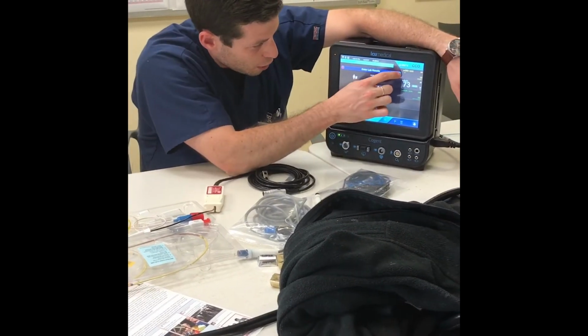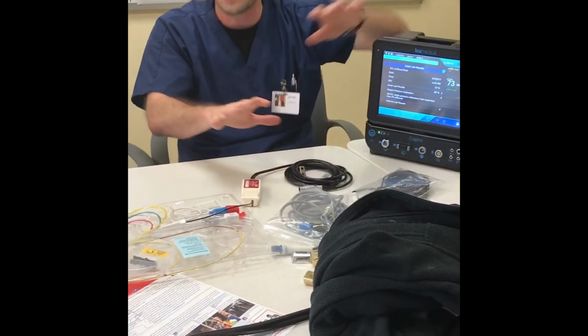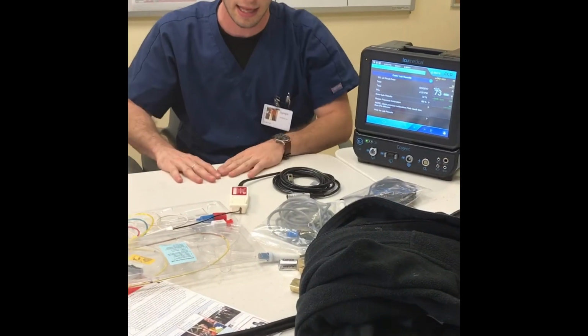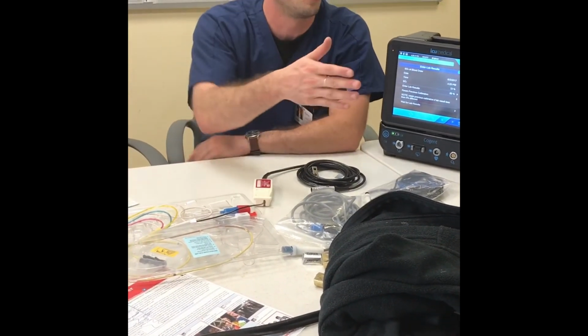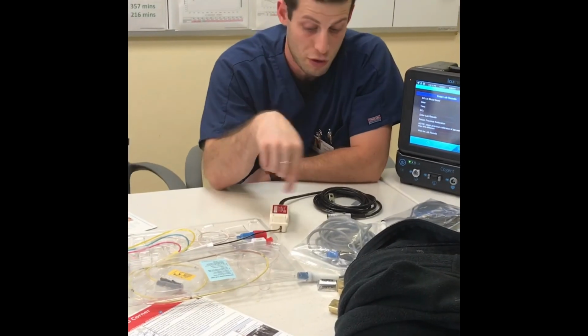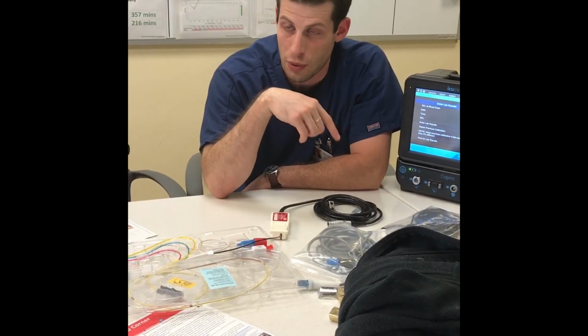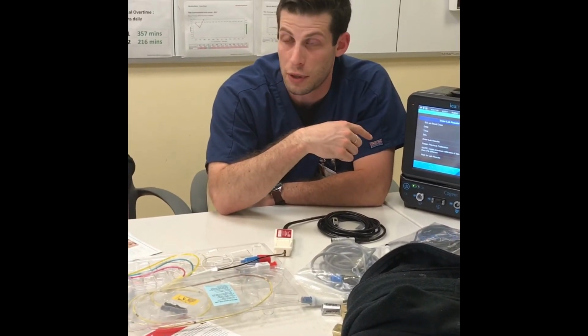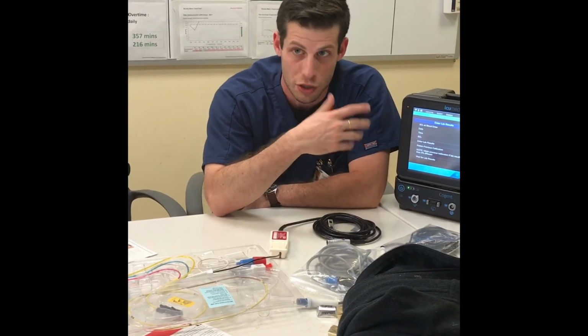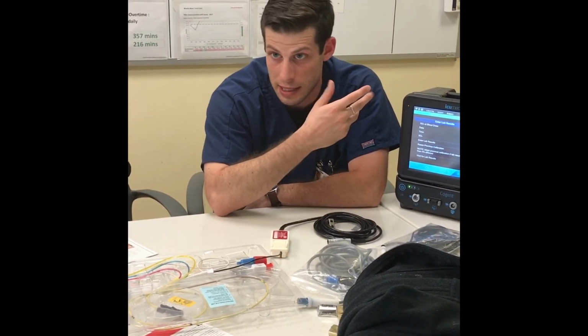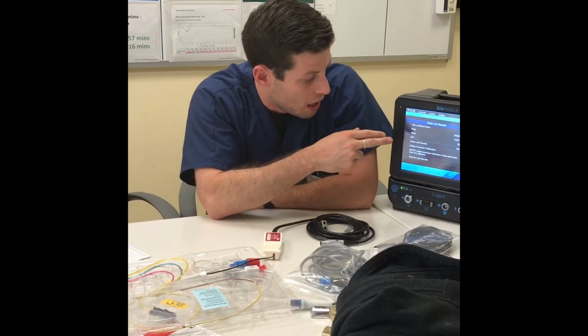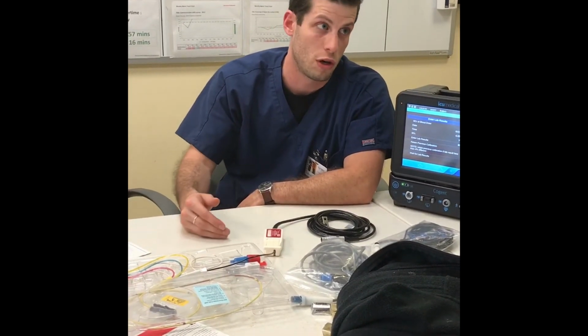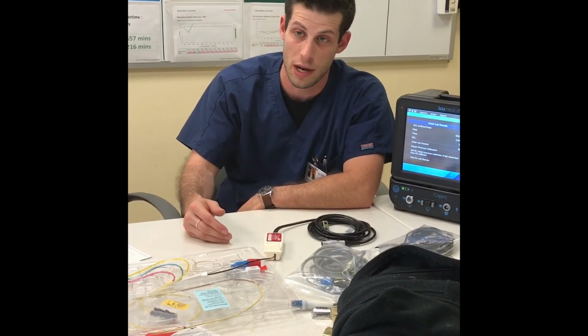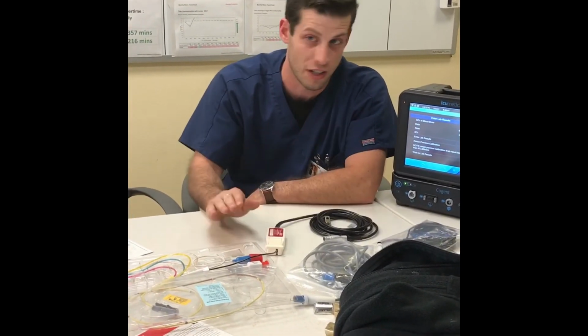I'm going to show you one thing when I go back to the screen. So I'm going to backtrack for 1 sec. Let's say, what I was telling you before, you're monitoring a patient, everything's hooked up, but the numbers don't look right to you. You're going to do this in vivo cal. It's not a bad thing to do, because you're really checking what the blood is, that mixed venous sitting right there. If the lab comes back within 4 percentage points of what the monitor's reading, you're not going to change the calibration, because that means that the monitor's accurate.